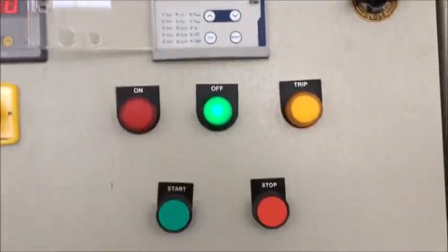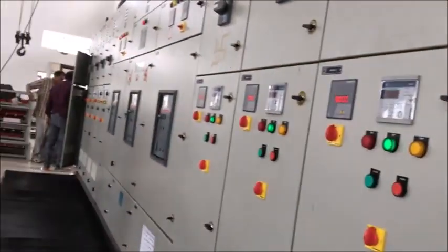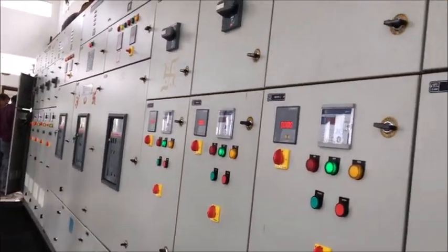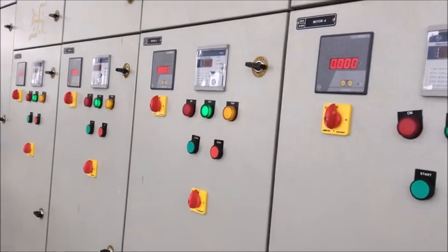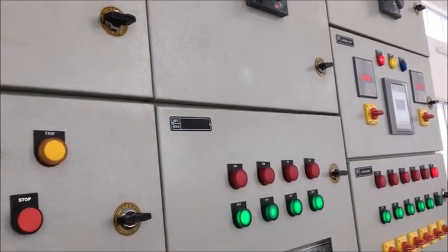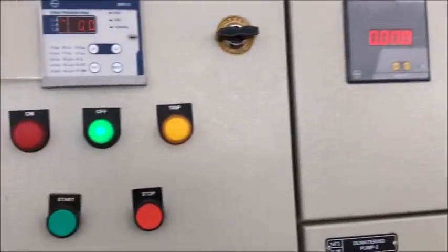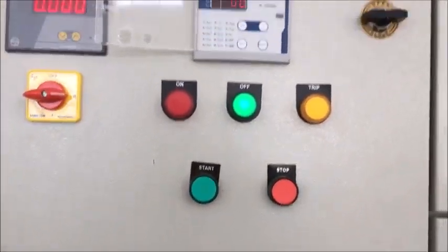So this is a simple setting of MM10 relay. Now one thing is very crucial about this relay is the base or full load current how to set because you can set from 2 to 10 amperes only. This is the entire panel which I am showing you.